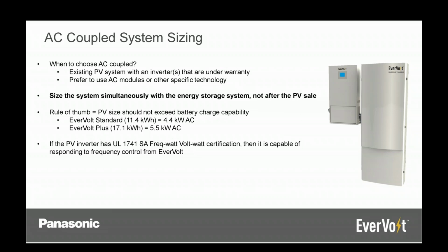Now, if it's a newer inverter that you're using and it's got the UL 1741 frequency-watt, volt-watt certification, then it is capable of responding to frequency control from EverVolt. So what this means is that your PV array can actually be a little bit larger than what the batteries can handle. As the PV array starts producing energy, we're basically going to shift our frequency to cause the PV inverter to shift its frequency, or move off of that maximum power point on the IV curve. That way, we're not producing as much power, everything is happy, and the power has a place to go.